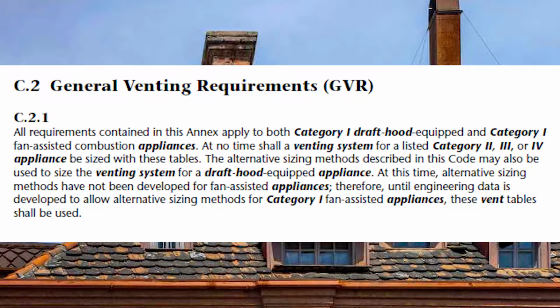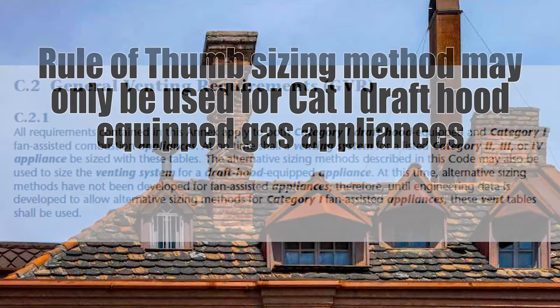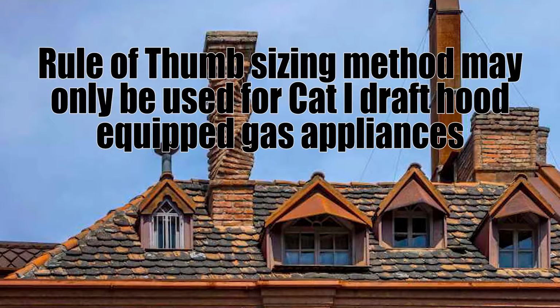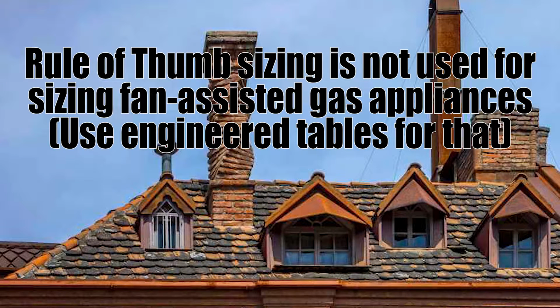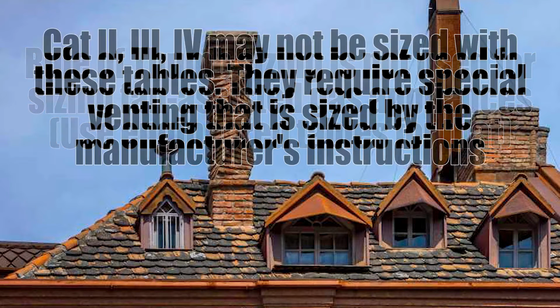The first GVR is C.2.1, which comes on page 174 of the codebook. It tells us when we can use the code tables, with what type of appliances, and when we can use alternative sizing methods, which we call the rule of thumb method. So the rule of thumb method can only be used on Category 1 natural draft appliances with draft control devices. As soon as we get to fan-assisted models, we cannot use the rule of thumb method. That's where we have to use these engineered tables.